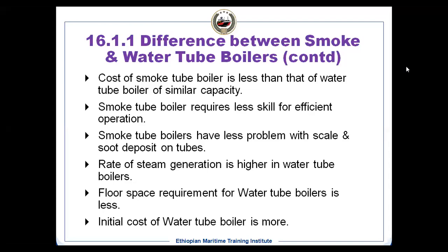We talked about the cost of a smoke tube boiler, obviously, because the construction is not that complicated as that of a water tube boiler. So the cost of a smoke tube boiler is much less than that of a water tube boiler. But the smoke tube boiler requires a little less skill from the ship staff for its efficient operation. A water tube boiler, as we just said, is not that forgiving when it comes to the skill of the ship staff who are operating it.